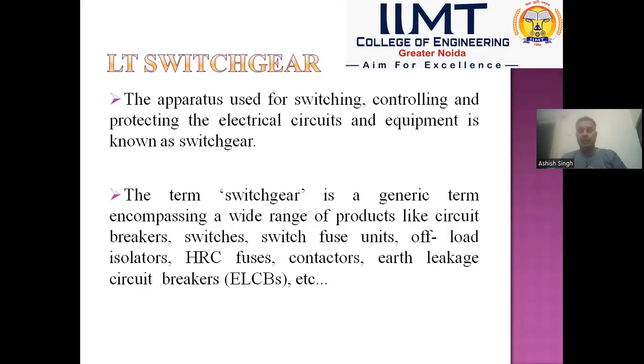As we know about low tension switchgear, first we have to know what is switchgear. Switchgear is basically an apparatus that is used for switching, controlling and protecting electrical circuits and equipment. That means any switching, controlling or protecting device is known as switchgear. The term switchgear is a generic term encompassing a wide range of products like circuit breakers, switches, switch fuse units, off-load isolators, high rupturing capacity fuses, contactors, earth leakage circuit breakers, etc.